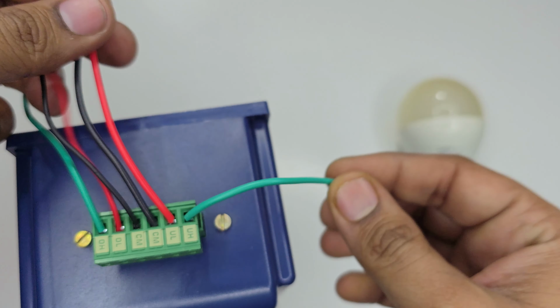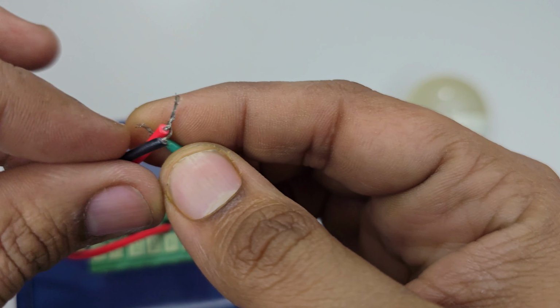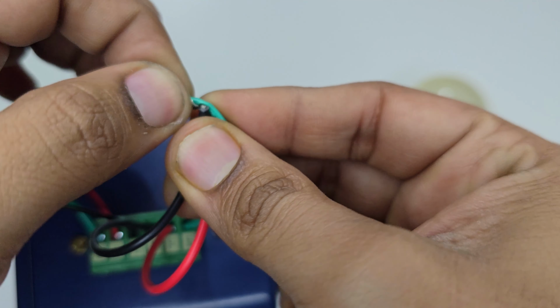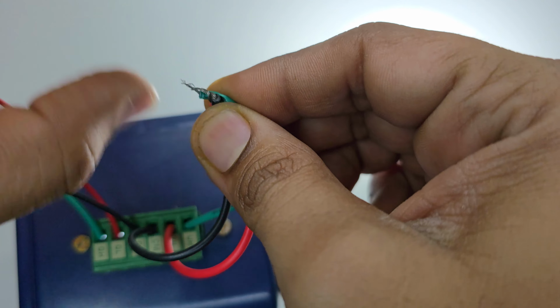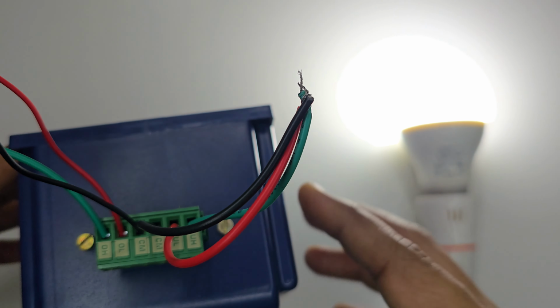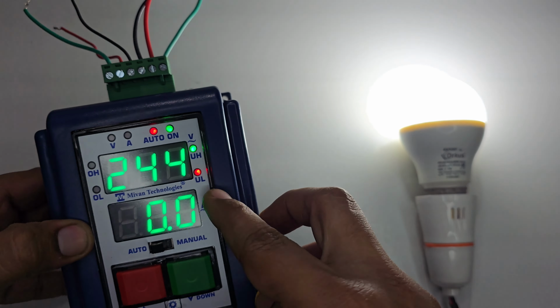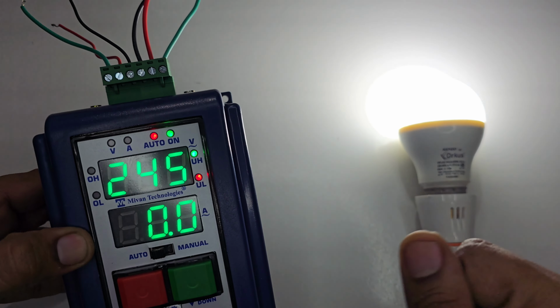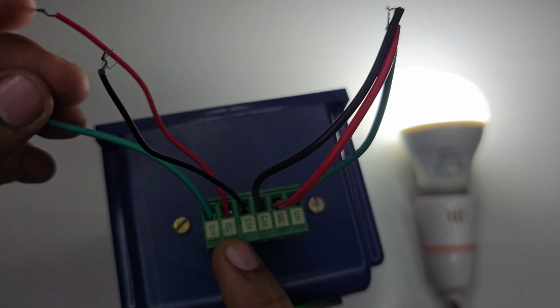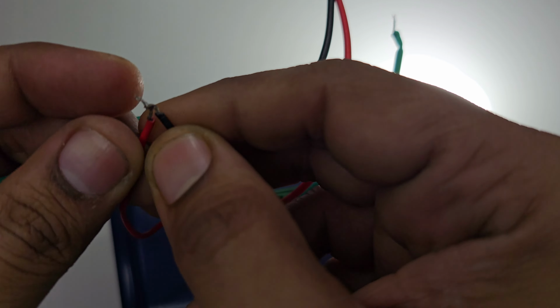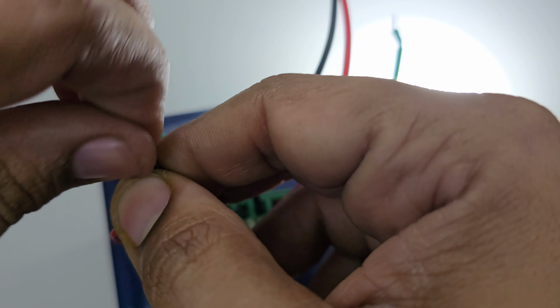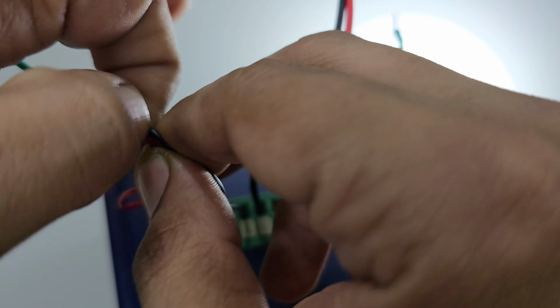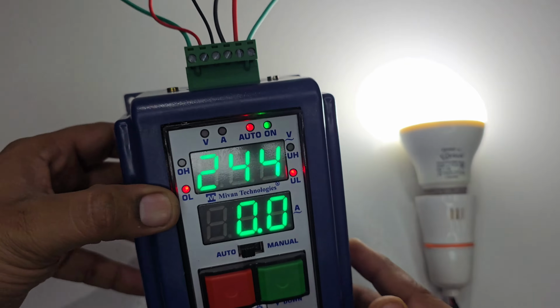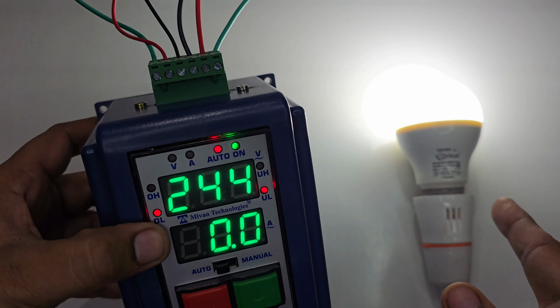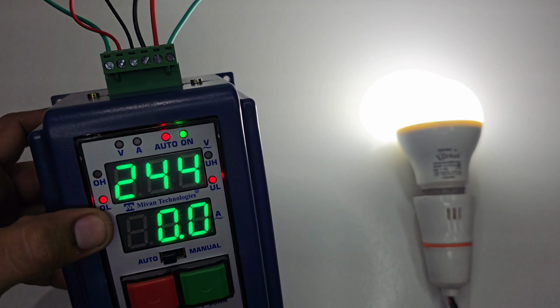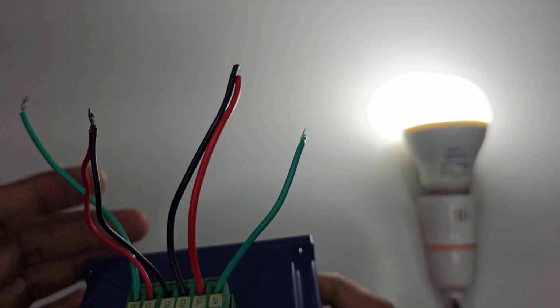Now short C, UL to the UH wire. When you short the C, UL and UH terminals, you can see the UL and UH indications and the bulb starts. Now short the C wire to the OL wire. When you short the C wire to the OL wire, you can see the OL indication and the bulb remains in an on condition. Now short all the terminals together.